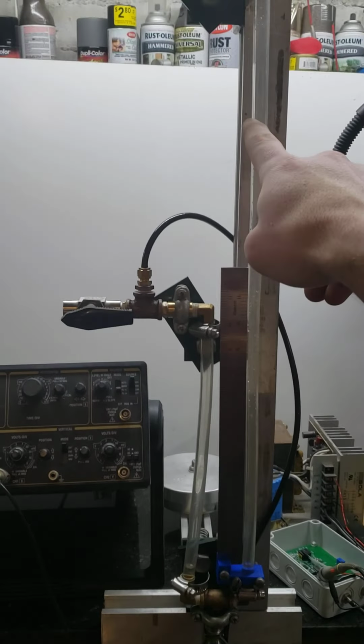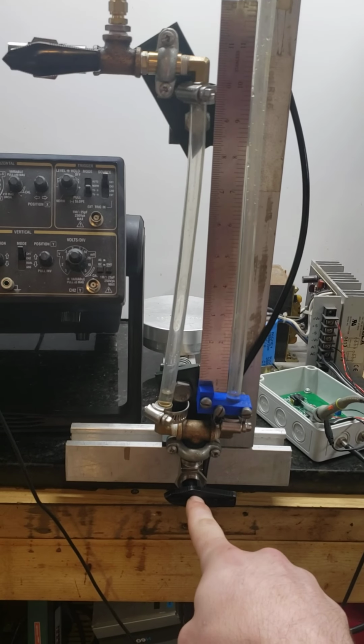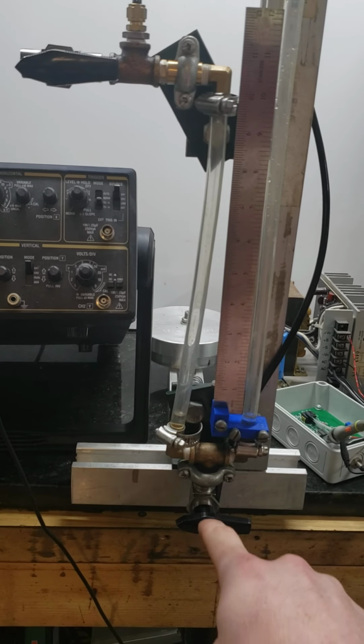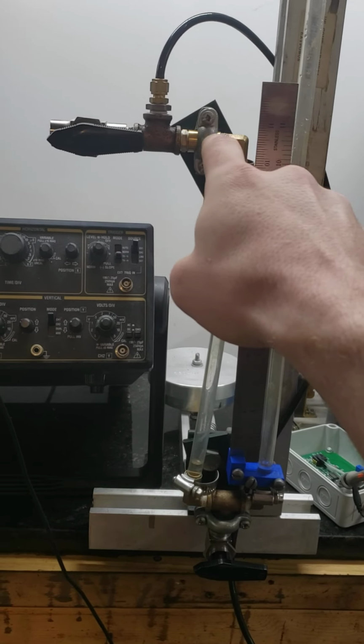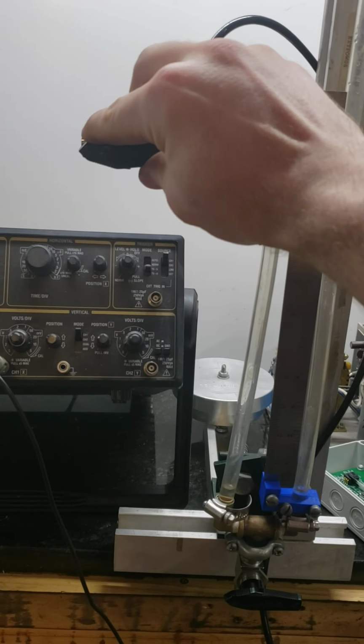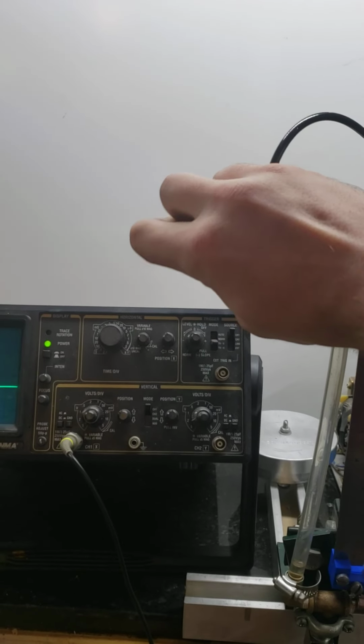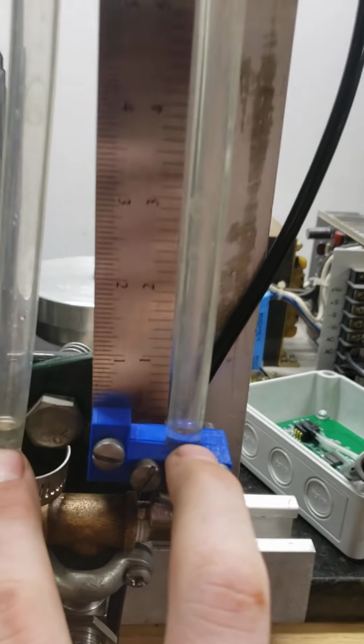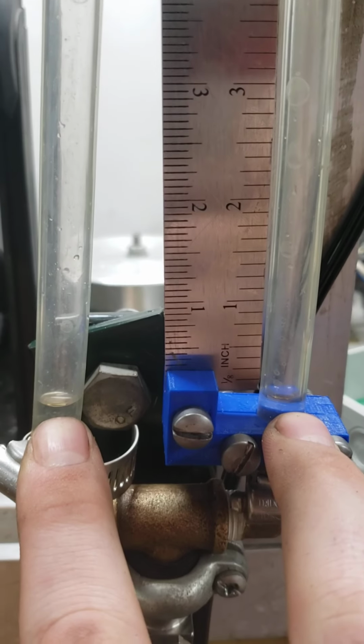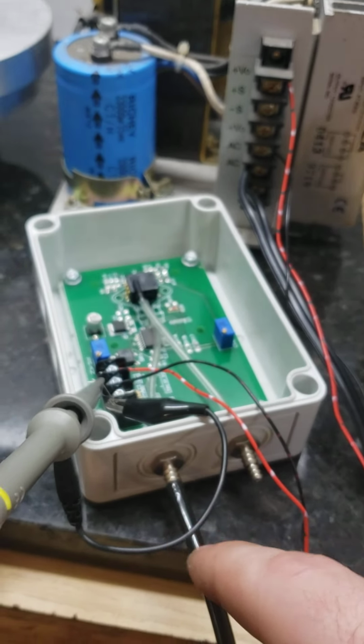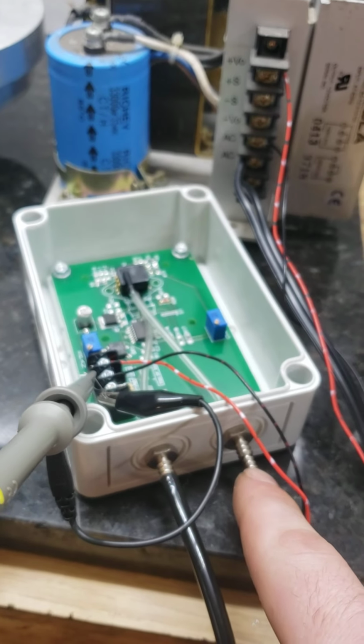As you can see, there is a tube going down with a valve to drain the water, and then up here we have a tube that leads to a T with a valve that, when we open that, the level of the water in these two tubes will equalize, and that'll mean that the black tube that is leading to the high pressure side of this sensor will be at atmospheric pressure, just like the low pressure input.